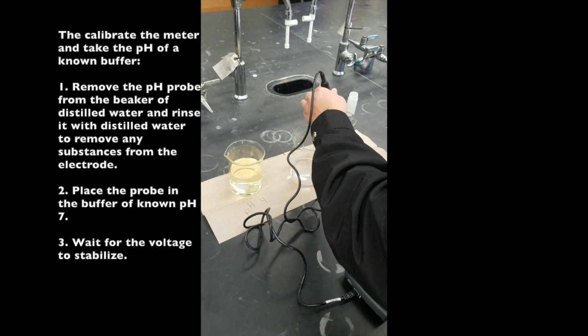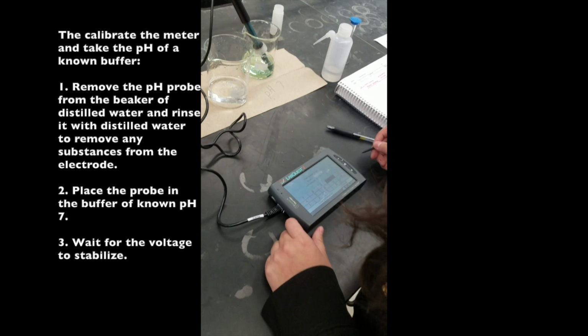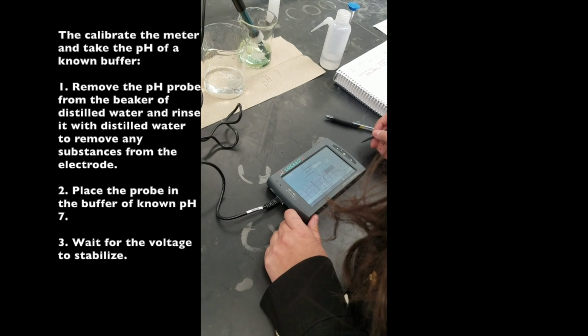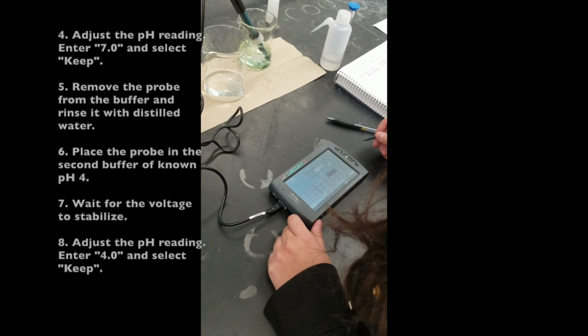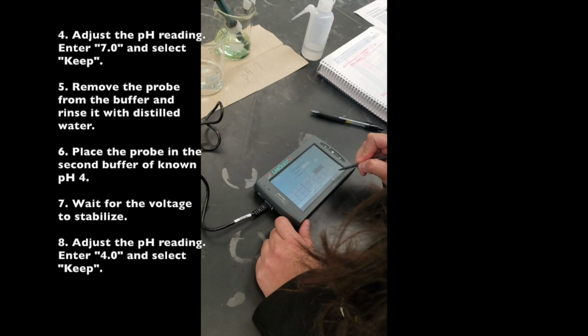Begin by removing the pH probe from the beaker of distilled water and rinse it with distilled water. Place it in the buffer solution of known pH 7. Wait for the voltage to stabilize. Enter 7.0 and select Keep.